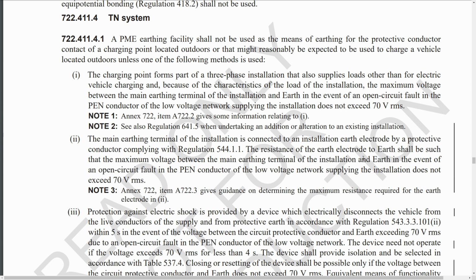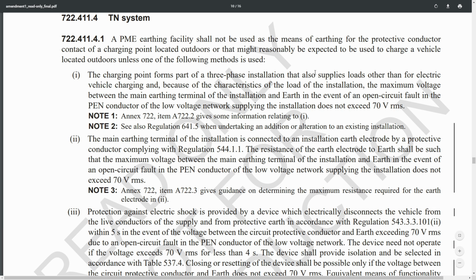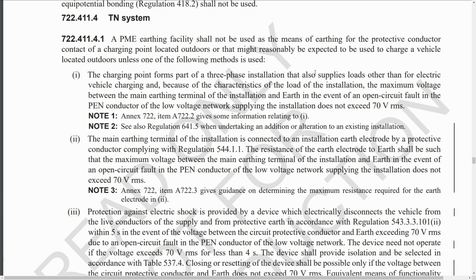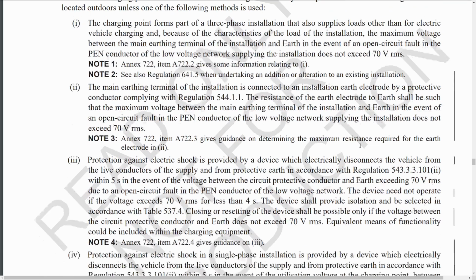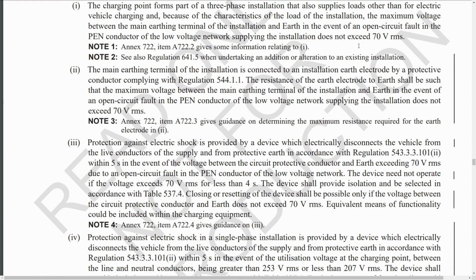So this hasn't changed, it's still in there, and it's one of the things which really is so impractical and unlikely that it's not actually going to happen, because a completely balanced 3-phase installation is pretty rare and never going to happen on a domestic anyhow, so not particularly useful. And again, it hasn't really changed. The only thing that has changed here is note 2, and note 2 basically says the same thing, they've just rearranged it slightly, so it now says when undertaking an addition or alteration to an existing installation, and previously it said when undertaking alterations and additions. So again, it's the same wording, someone's just rearranged it for some personal reason. So that's pretty much the same, but you're never going to use it because it's such an unlikely scenario that it's not going to happen.